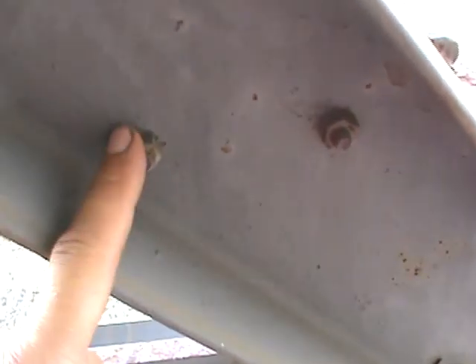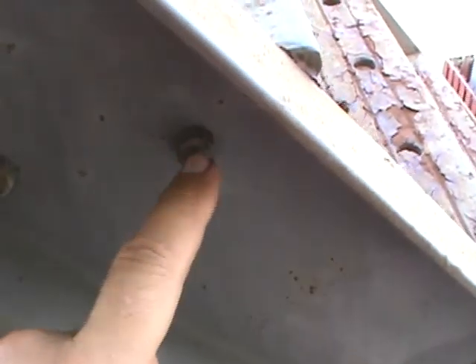So basically these bolts, which are undersized, they usually have 3/8 minimally. These are all like 5/16 or quarters, and these easily blast through and drop without a problem. So I'm going to suspend the inspection at this time and talk about from here down what's going to happen on all the floors up above.